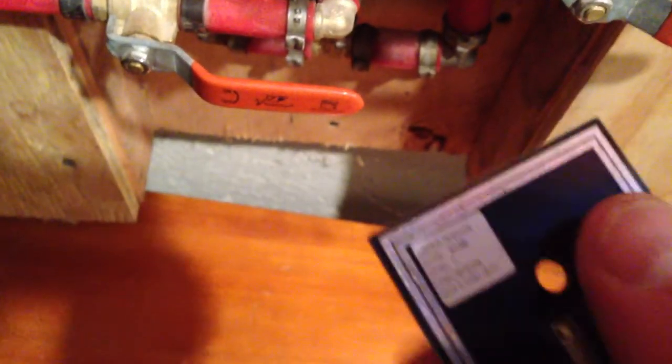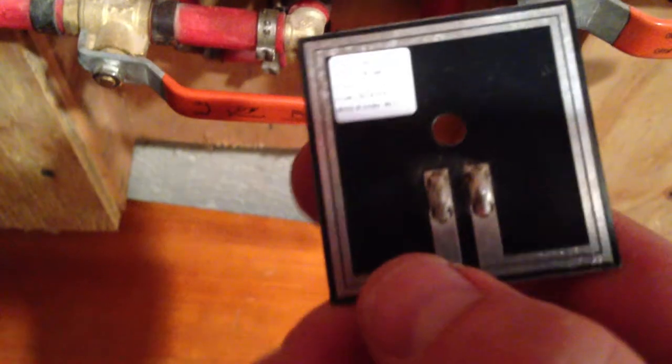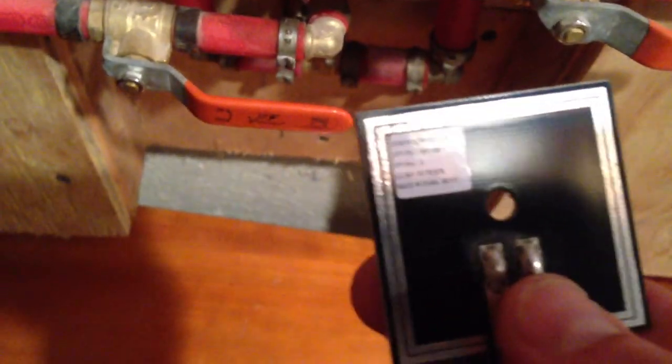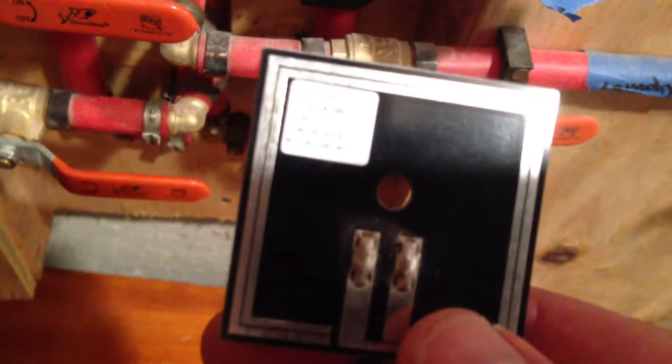So here's the other end of the sensor. You can splice these. It's just two wires. And if you look at it, on one side it says this side up, www.protectedhome.com. The other side faces down. If you can see, it's basically a normally open connection. It's just two connectors and if you make the circuit across any of these, it almost looks like a circuit board. If any water gets on there, it'll make the connection. And then the main part of it, which is over there, will detect the alarm.